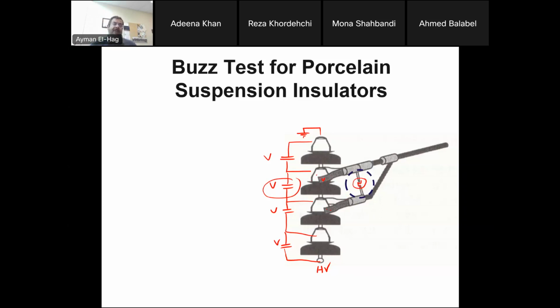Now let's imagine the other way around. If there is an internal defect, okay? So this insulator here, internally, there is a defect. It's like a short circuit internally that you cannot see. So if there is an internal defect here, this insulator will not hold the voltage. It will be like a short circuit. There is no voltage there, okay? And the voltage now, instead of being distributed among 4 disks, will be distributed among 3 disks only. So each disk will have a slightly higher voltage. Now, when you bring your device across that insulator that has 0 voltage, there will be no buzz, no sound. You will not hear anything because there's no potential difference between these two points, okay?